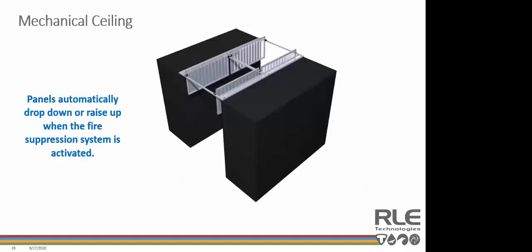Another option to use when using cold aisle containment are mechanical ceilings. A mechanical ceiling can be built to either raise up or drop down if there's an event, and these components link or are wired directly into the fire suppression system in your data center. So when the fire suppression system is activated, the ceiling panels automatically raise or drop to open the contained area. In the case of a false alarm or a test, the system can be easily reset, and it also uses the same drop-away panels as our standard ceiling, so redundancy is built into the system. If for some reason the mechanical part failed, those ceiling panels would still shrink at 165 degrees and drop out of the mechanical ceiling.